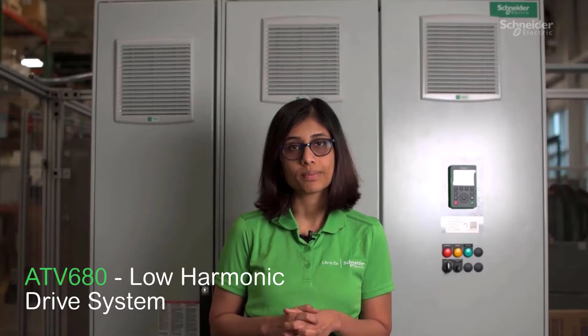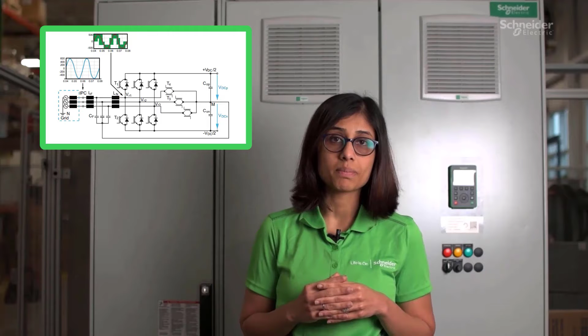Both our ATV 680 and 980 series of drives come with Schneider Electric's patented 3-level active rectification design along with an advanced LCL filter on the input side of the drive. There is also an additional link in between this input filter and midpoint of the DC bus, which helps us deal with common mode voltage, a very common issue that can be seen with 2-level active rectification design.